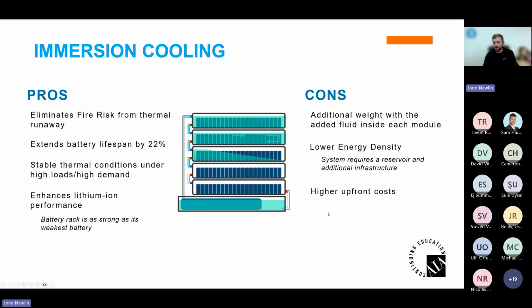This also has a higher upfront cost, and one of the reasons is because you get a full system redesign with immersion cooling. Liquid plate was unique in that it could be added to previous designs, kind of grandfathered in. So it's easier to adapt, maybe adding $15 a kilowatt hour to add a liquid cooling system - great, we have a metric, we can slap it on, it's good. With immersion cooling, we are fully redesigning down to the module level because we need to create modules that hold this.